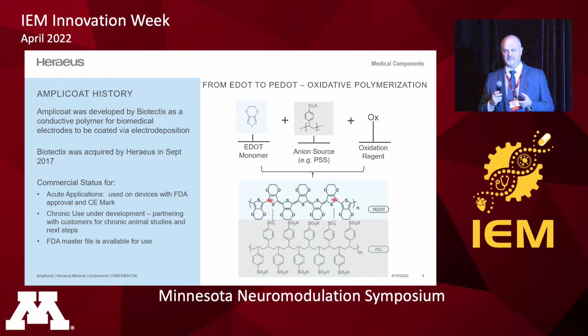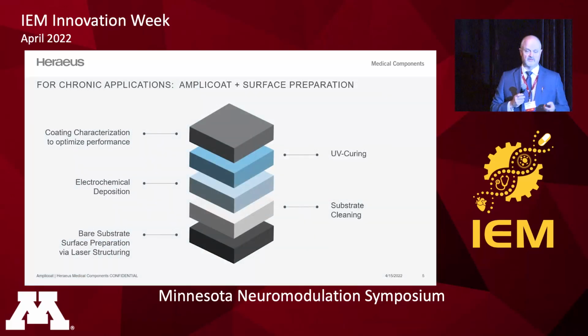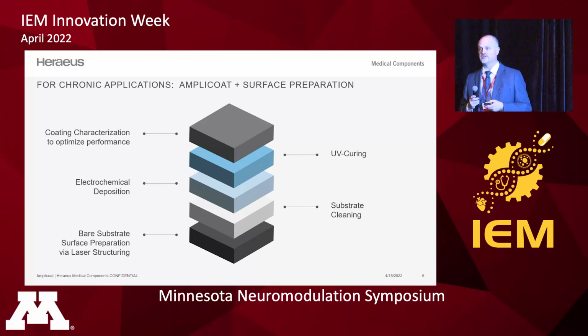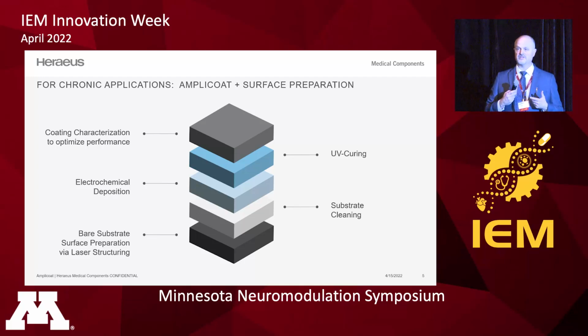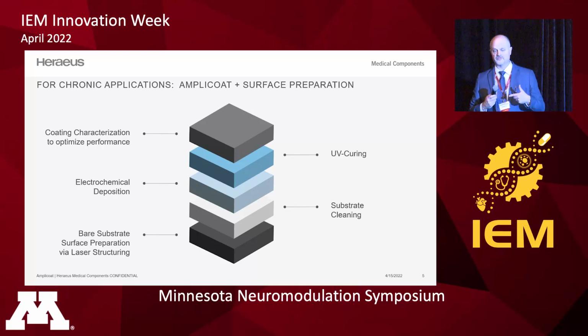So the EDOT to PEDOT oxidative polymerization reaction is shown right here, and it's a pretty common item. PEDOT's been around for a long time, but what Jeff was able to do, what Biotectix was able to do, is to change the additives to make it biostable. The process that we have for chronic applications is Amplicoat Plus, and that Plus is surface preparation. What we do is we laser structure the electrode to improve its adhesion properties. Then from there, we clean it, then we do the electrochemical deposition of the Amplicoat, we do a UV curing process, and then we can optimize the coating for your performance.